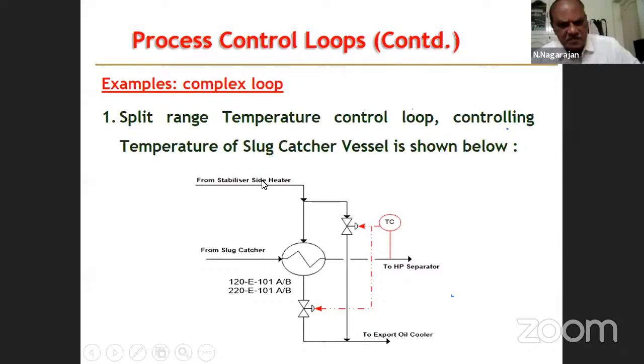The heat is coming from another equipment, from the stabilizer side heater. There is another heater outside that is coming here. This is one parameter. Main flow from the slug catcher is passing through the exchanger. This is the main process flow stream. This is another stream which is used to heat the crude oil. So what we do, we want to control the temperature of the main process stream, the hydrocarbon stream. You measure the temperature here and try to control the bypass here. And as I said, the measurement is 1, but action is 2.